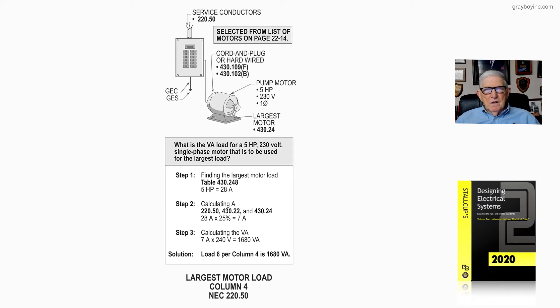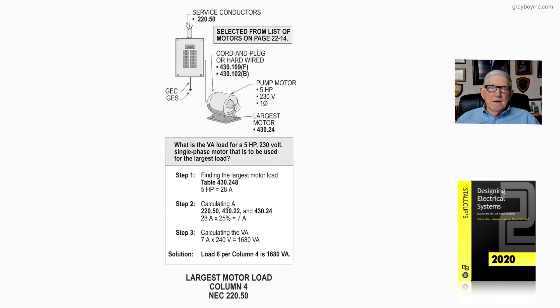So we're going to go to 430.24, and to get the full load current rating of this motor, we reference table 430.248. You would want to reference 430.6A1, which refers you to table 430.248 to select the full load current rating of single phase motors. That 5 horsepower motor would be 28 amps as listed in that table.